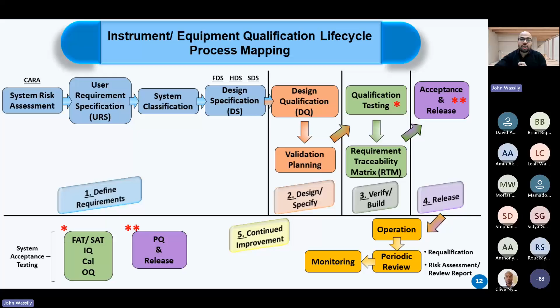And finally, we go for the acceptance and release of the piece of equipment. This will be by performing PQ testing, performance qualification testing, and I will take you through how this testing will be performed. This is the final stage, which is the release stage. By reaching this stage, I am releasing the piece of equipment for routine operation and routine use in vaccine manufacturing. And then periodically, I shall pass through this piece of equipment, making sure it's maintaining its initially qualified state by performing periodic review and monitoring. This is a quick and brief overview of the equipment qualification life cycle. I know it's a bit dense, but this is how the equipment qualification should go.